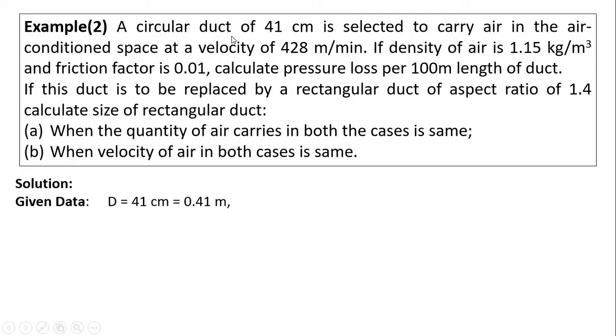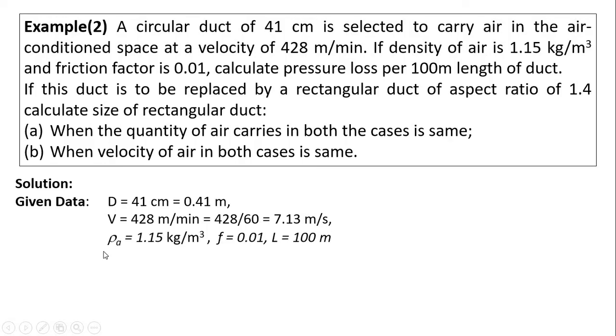Writing the given data: circular duct diameter D = 41 cm = 0.41 m. Velocity of air = 428 m/min; dividing by 60 gives V = 7.13 m/s. Density of air = 1.15 kg/m³. Friction factor f = 0.01. Length of duct = 100 m, and aspect ratio a/b = 1.4.